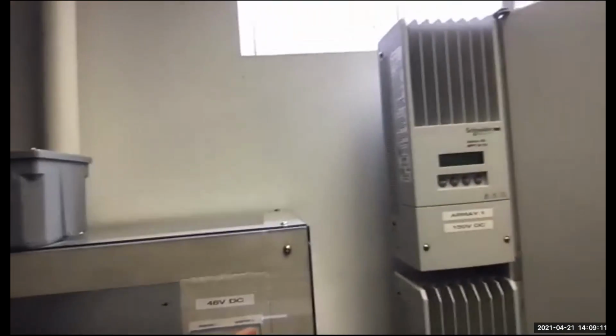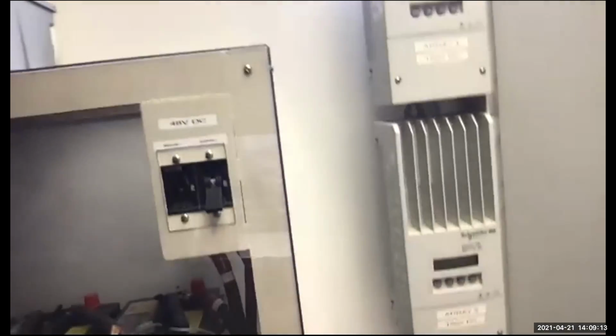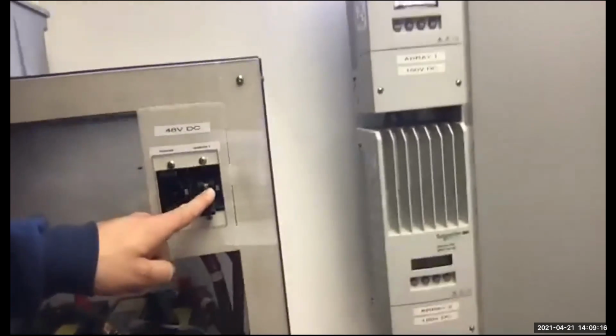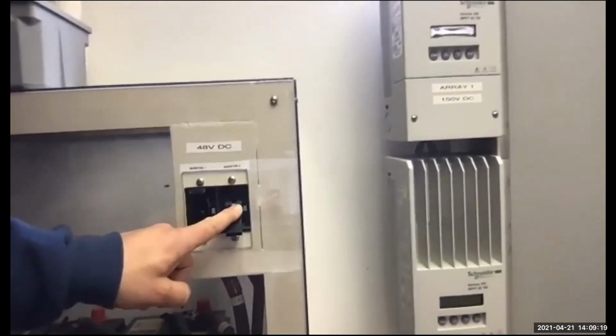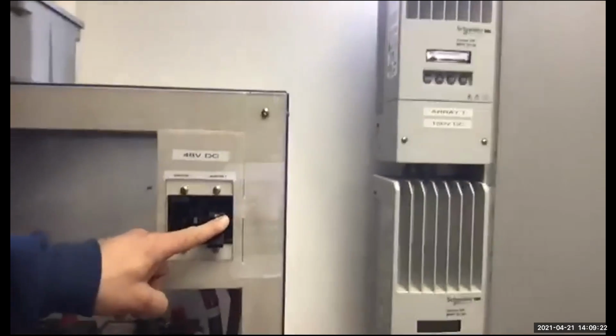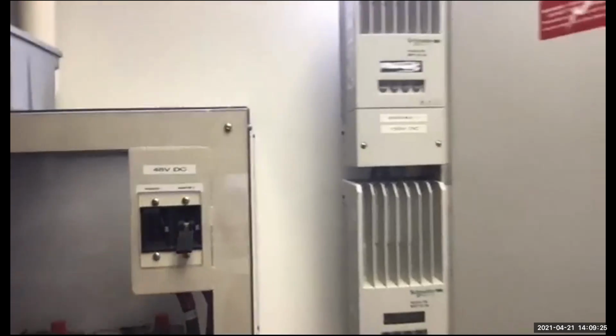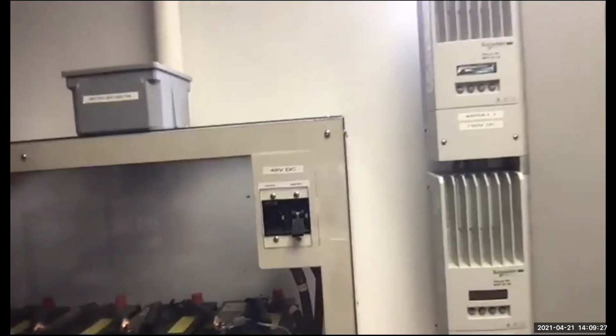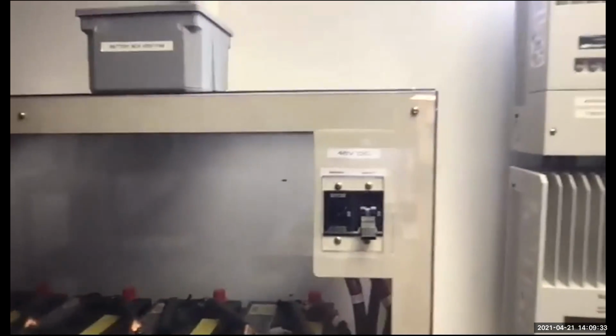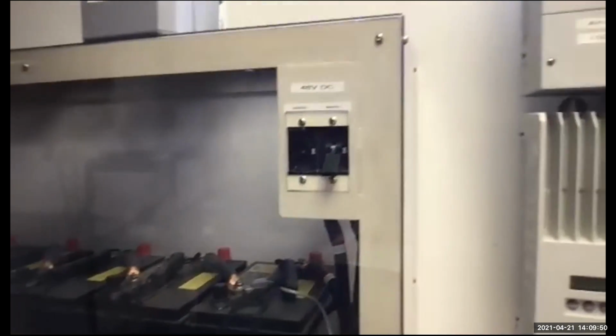So safety-wise, we want to turn that off, right? So we got redundant isolation. Remember how I said we got breakers between this and that, and disconnects between this and that. That's what we want. So that's a 250 amp breaker. We can see our wires. We've got a negative cable coming to our batteries all the way down here on this side. We got our negative cable right there. And then they are positive, negative, positive, negative, positive, negative, positive, negative. They are wired in series all the way down to here.